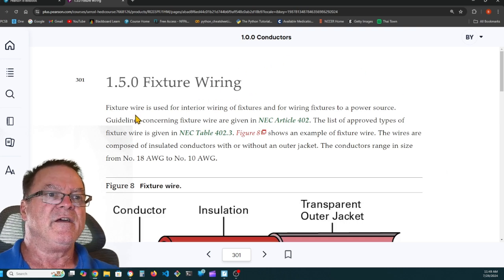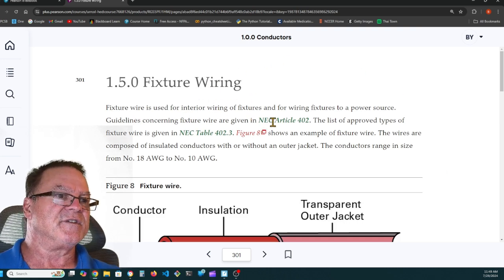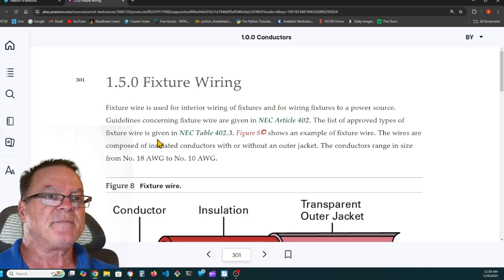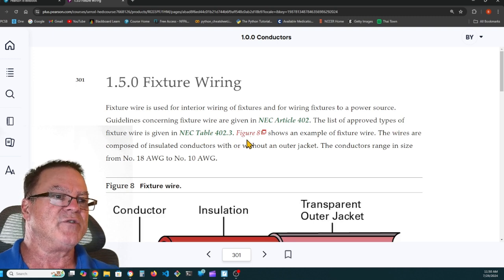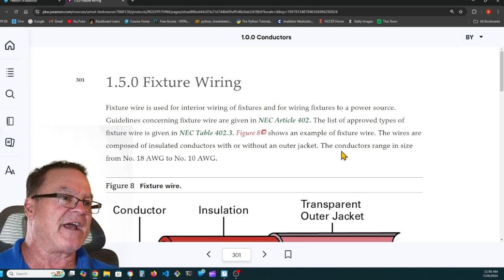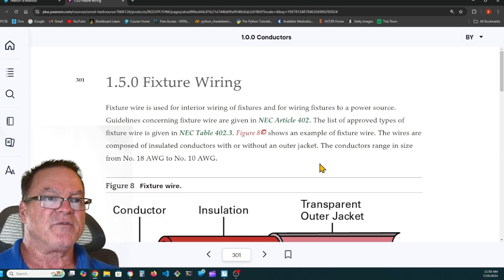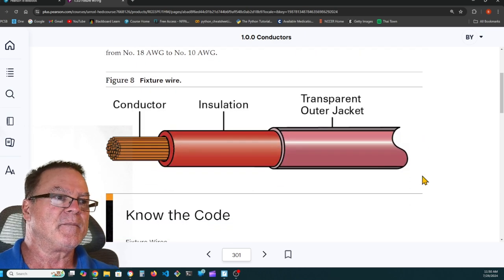Fixture wiring. Fixture wire is used for interior wiring of fixtures and for wiring fixtures to a power source. Guidelines concerning fixture wire are given in Article 402. The list of approved types of fixture wire is given in Table 402.3. Figure 8 shows an example of fixture wire. The wires are composed of insulated conductors with or without an outer jacket. Conductors range in size from number 18 to number 10. So here's a transparent outer jacket.